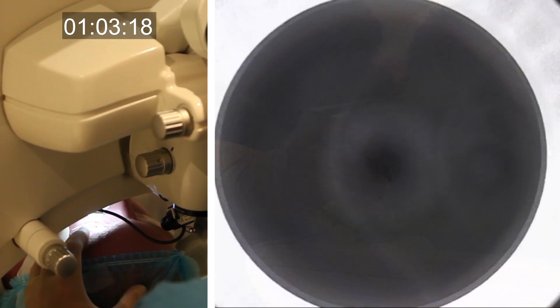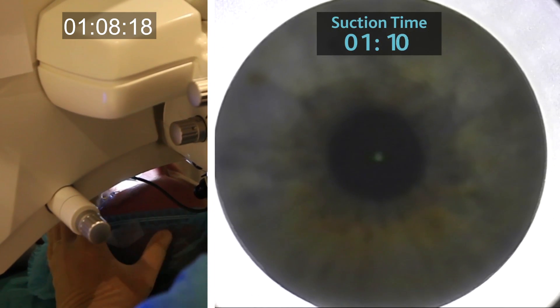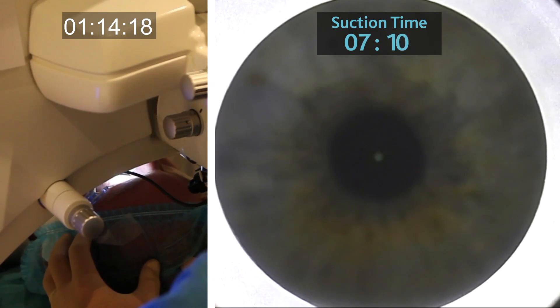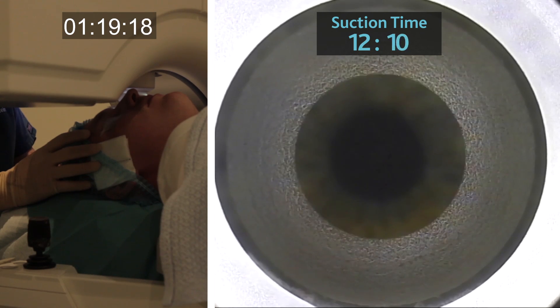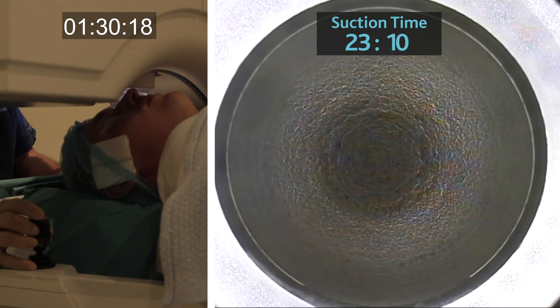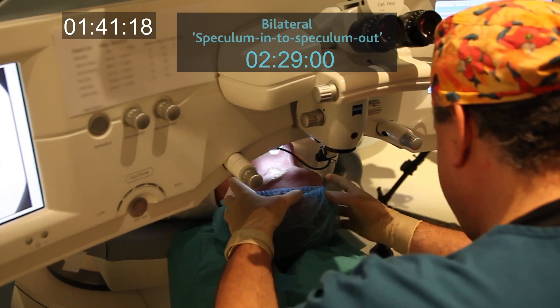At the moment of contact between the cone and the cornea, a meniscus tear film appears, at which point the patient is able to see the fixation light very clearly because the vergence of the light is adjusted according to the patient's refraction. The combination of surgeon coaxial view and patient coaxial fixation results in flap or lenticule creation that is centered on the visual axis. Forward or backward movements of the patient's head during flap creation are compensated for instantaneously by a continuous force feedback servo control mechanism that adjusts the bed height to maintain a constant force of the contact glass onto the cornea.